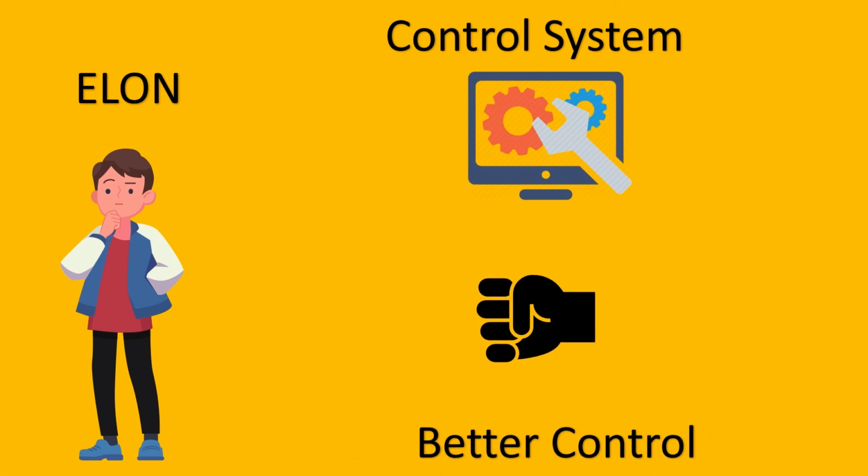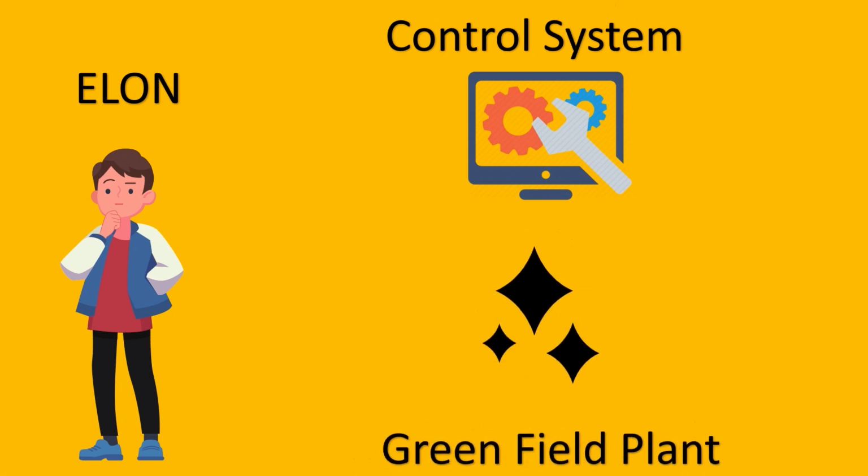However, my personal preference has been to do it in control systems. Why? Because in the field you don't have that much control. Maybe the transmitter vendor is changed, or sometimes certain transmitters are bought from different vendors, but usually the control system is bought from one single vendor. So you can tell the vendor to do the square root extraction for all the cases. So you have better control over whether square root extraction has genuinely taken place or not.